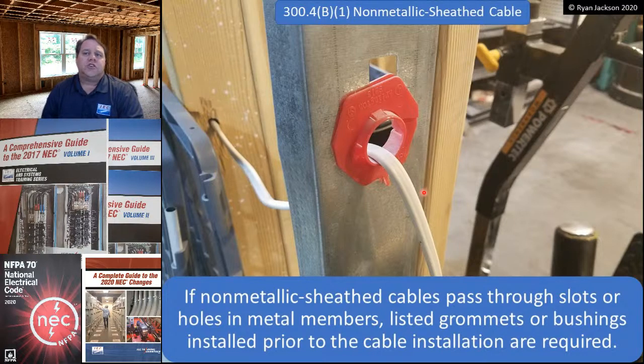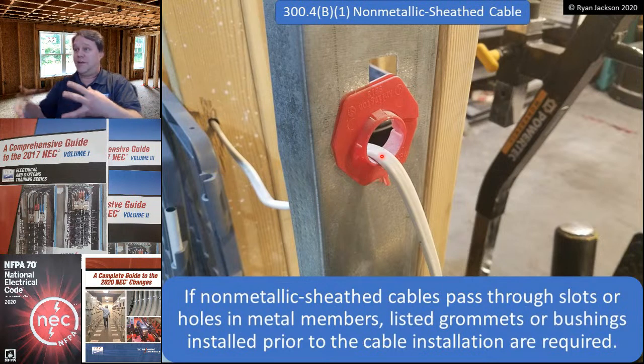300.4(B), nonmetallic sheathed cable. If nonmetallic sheathed cables pass through slots or holes in metal members, such as what we're looking at here, listed grommets or bushings that are installed prior to the cable being installed are required. So I have to have some sort of a bushing or a grommet to protect my cable, and that makes perfect sense. If you've ever pulled MC cable through metal studs, you know the racket that it makes as it drags through the hole. You can imagine that pulling NM cable through steel studs, you would just end up with a nice big wad of white plastic when you're done.